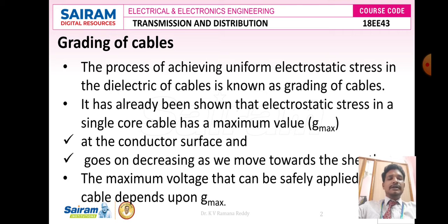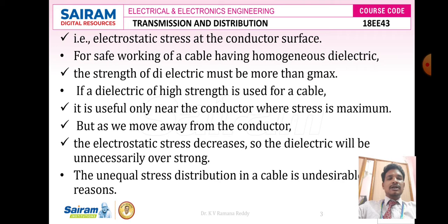The maximum voltage that can be safely applied to the underground cable depends upon Gmax, that is the electrostatic stress at the conductor surface. For safe working of a cable having homogeneous dielectric, the dielectric strength must be more than Gmax. If a high-strength dielectric is used, it is useful only near the conductor where stress is maximum. The impregnated paper near the conductor has high electrostatic stress compared to the metallic or lead sheath further out.